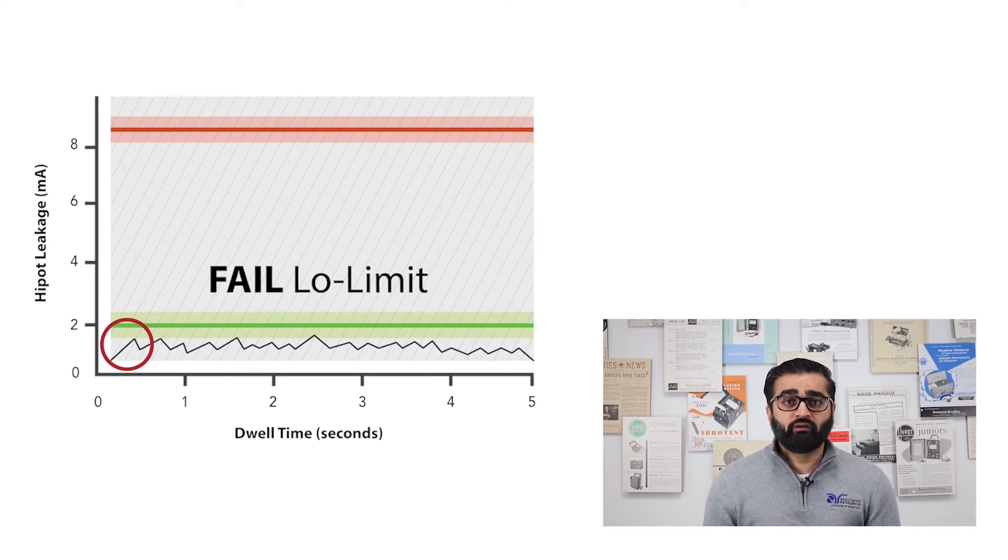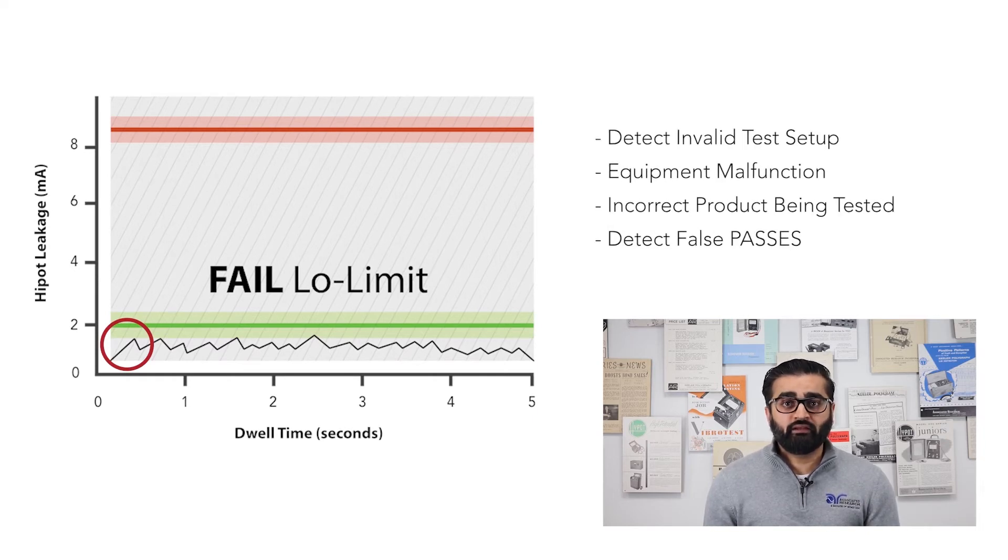Now let's take a look at the low limit parameter. This value doesn't come from any standards, but something that should be considered by all manufacturers. In an event that test cables aren't connected properly or if the test equipment malfunctions, this can result in no current being measured by the test equipment, creating what's known as a false pass condition.